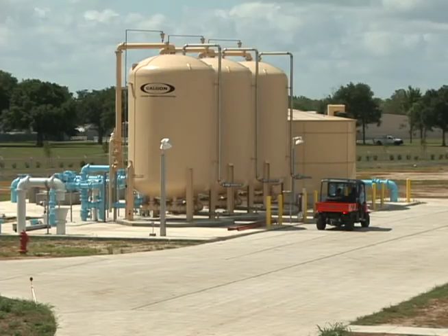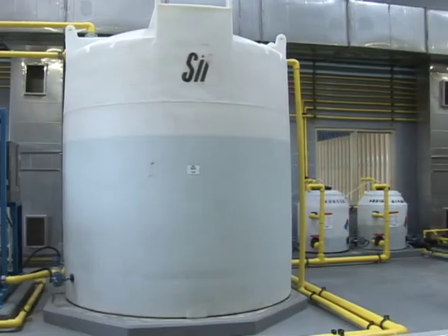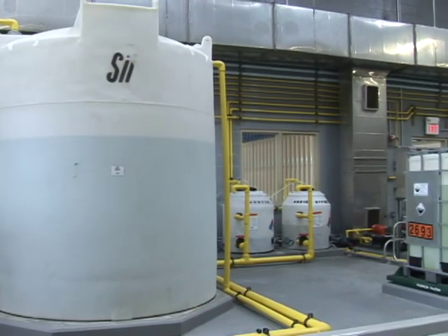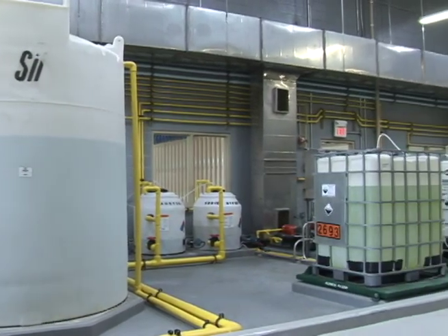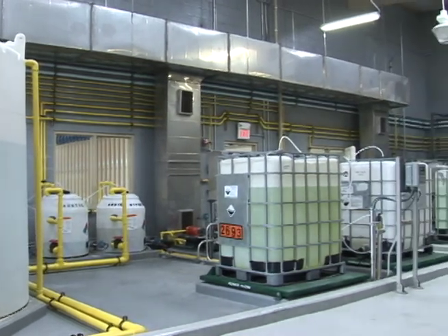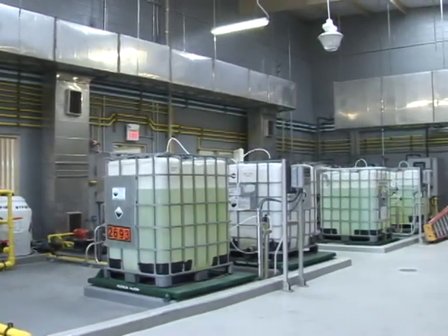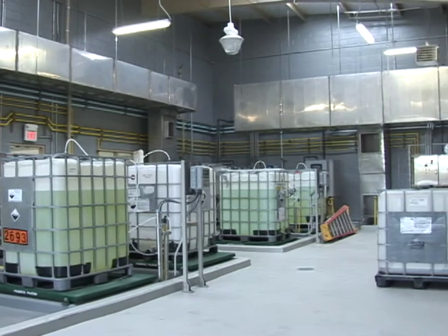Then during certain portions of the seasons, when we have algae blooms and things, we send it through the carbon filters, granulated activated carbon. And then it goes from there into the chemical treatment, where it goes through chlorine dioxide, which is a very strong disinfectant that oxidizes everything in the water, organics in the water.